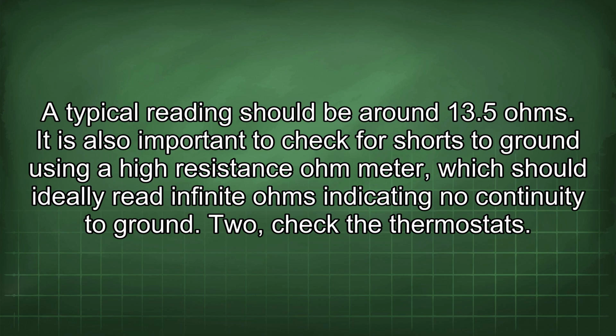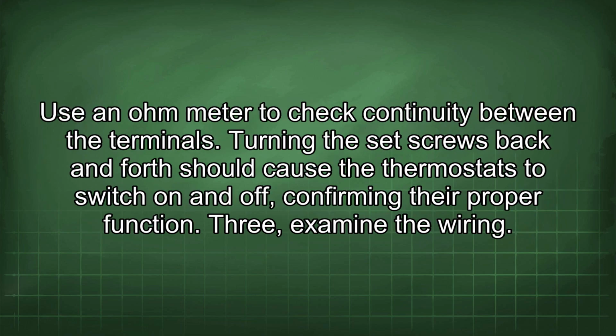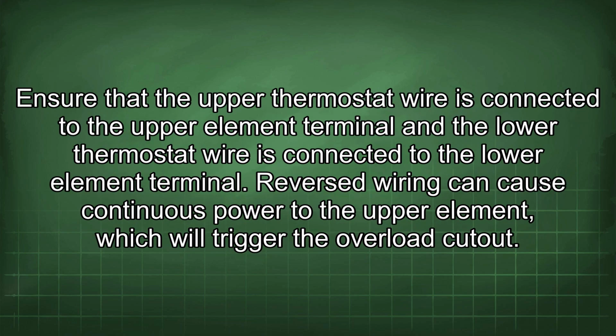2. Check the thermostats. Use an ohm meter to check continuity between the terminals. Turning the set screws back and forth should cause the thermostats to switch on and off, confirming their proper function. 3. Examine the wiring. Ensure that the upper thermostat wire is connected to the upper element terminal and the lower thermostat wire is connected to the lower element terminal. Reversed wiring can cause continuous power to the upper element, which will trigger the overload cutout.